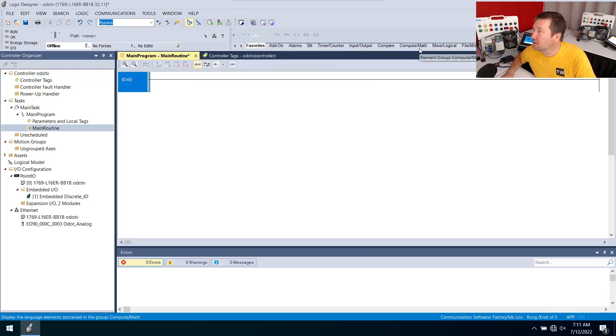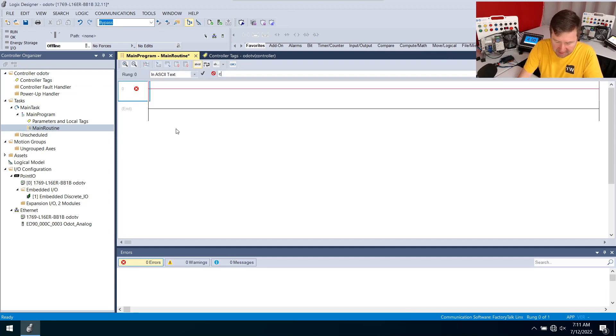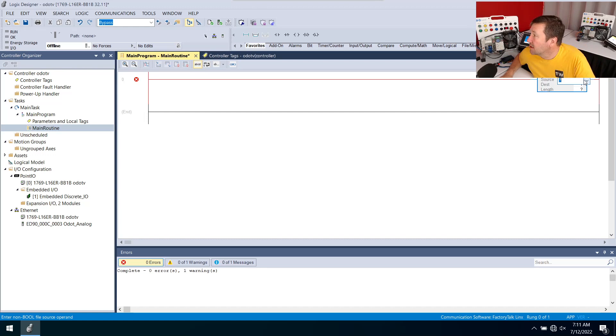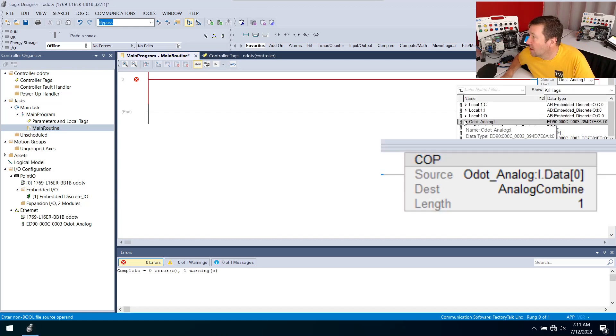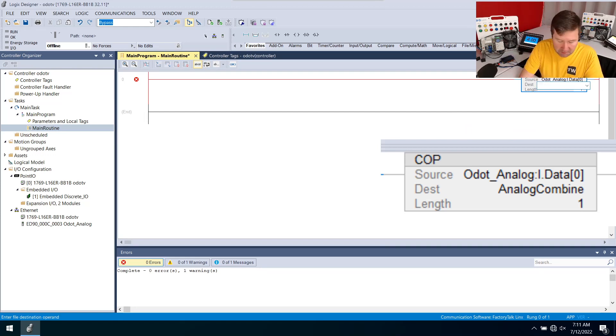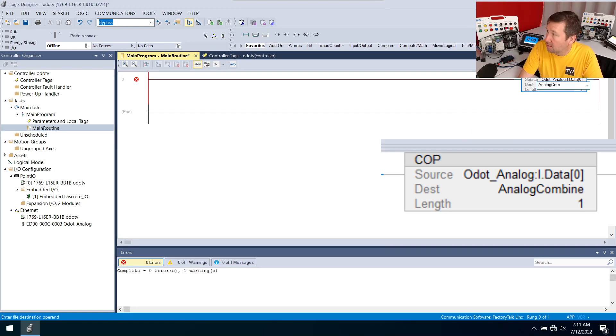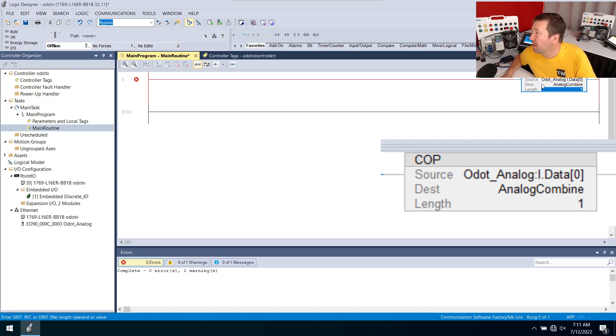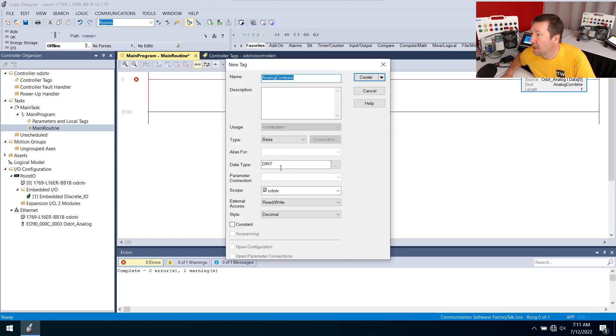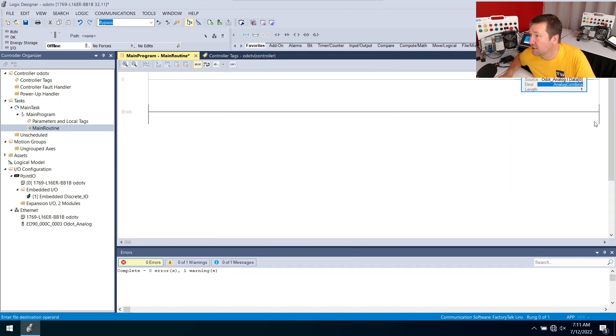We're going to use a copy instruction, I'm just going to type COP enter. Our source is going to be ODOT analog colon I data zero. Then I'm going to copy it to analog combine and the length is going to be one because it's based off the destination. I'm going to right click this, new, and I'm going to keep it as a double integer because two single integers make a double integer.